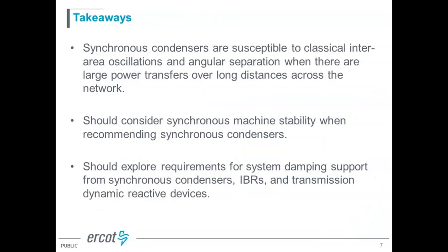So the key takeaway is that we do have condensers to provide system strength and improve grid voltage stability, but they are synchronous machines. So they are susceptible to typical angular and inter-area oscillations as well, especially under large power transfer over long distance. And this condition is commonly associated with renewables in many other regions, at least in ERCOT.